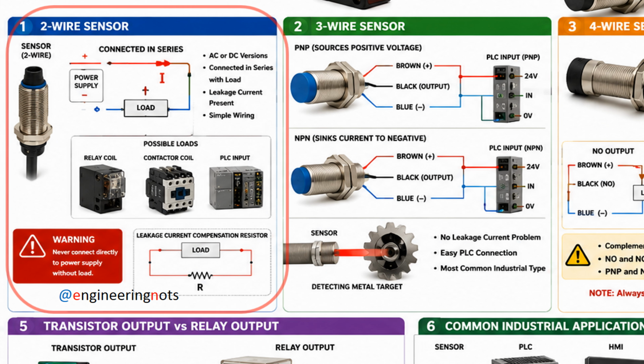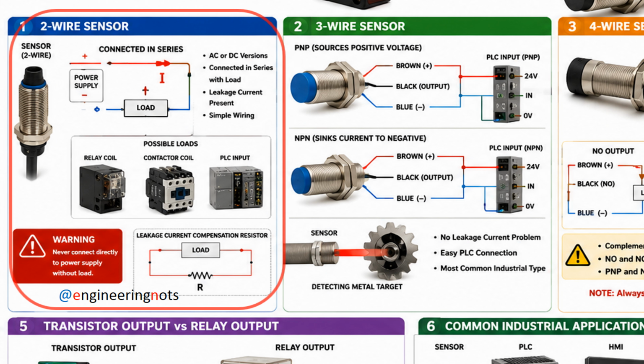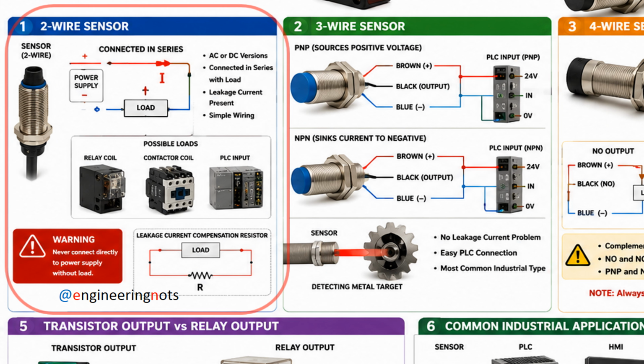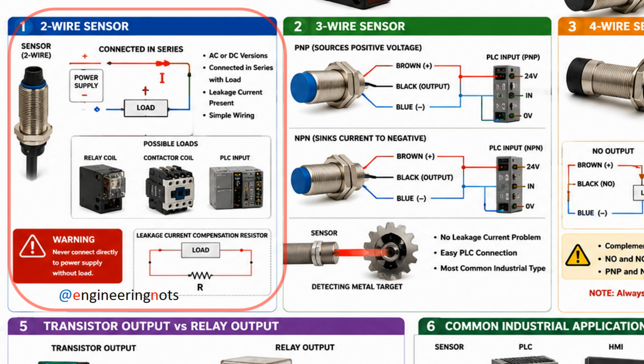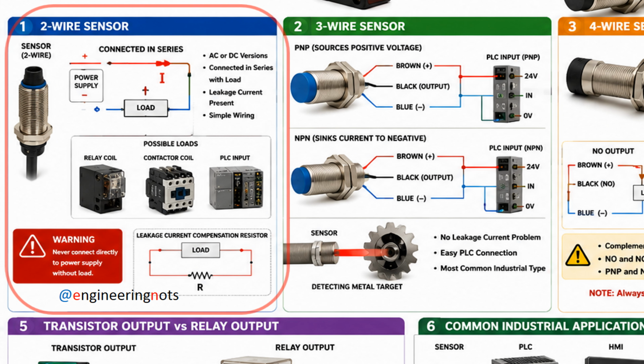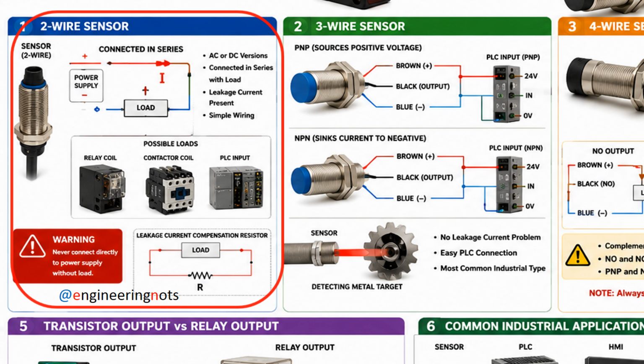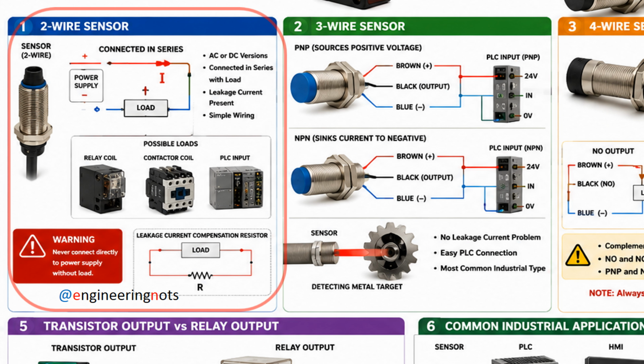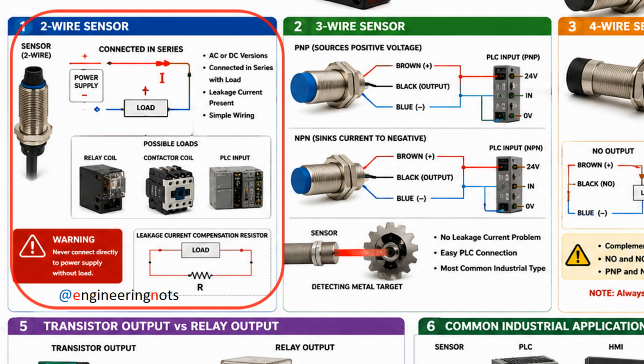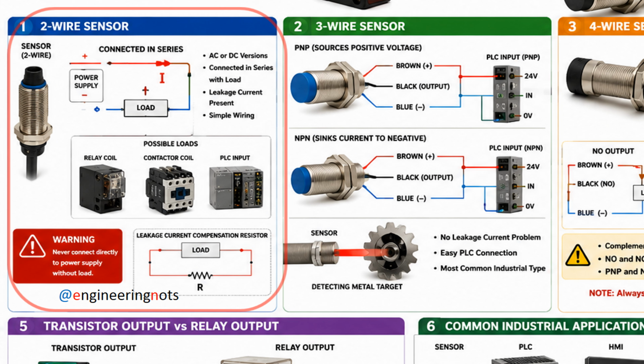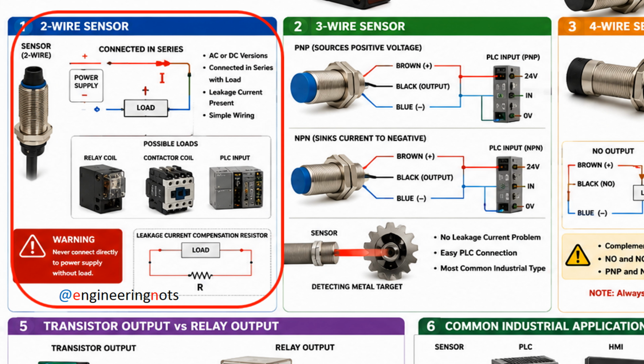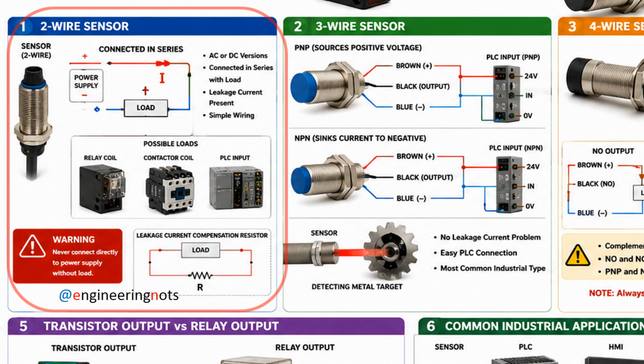What is leakage current? Now we come to the most important characteristic of two-wire sensors. Even when the sensor is off, a very small amount of current still flows through it. This current is called leakage current. The reason for this is the internal electronic circuitry of the sensor. Why leakage current can be a problem? In many loads, leakage current is not important. However, if the load is very sensitive, such as PLC inputs, electronic input cards, highly sensitive relays, this leakage current may cause unwanted operation. Sometimes, it can even be observed that a relay remains energized after the sensor has been switched off.